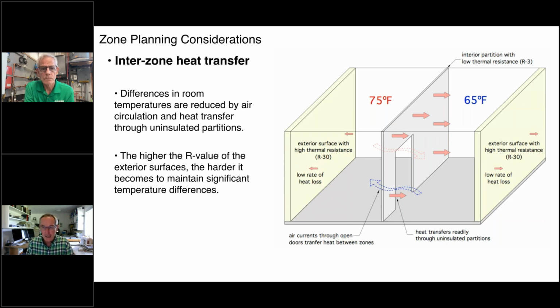Even if we shut off the heat in the space at 75 degrees, we would find that it would eventually equalize very close to the other temperature and vice versa. And the higher the thermal resistance of that building envelope, the more difficult it is to maintain significant temperature differences between these spaces. Now, if there's some reason where you really need to maintain significant temperature differences, you can insulate the partitions and basically keep the door closed, or possibly even use an insulated door. But most homes are not built that way. So again, consider interzone heat transfer and move away from the idea that I could keep bedroom number 1 at 65, I could keep bedroom number 2 at 75, and I can have an uninsulated partition between them, and both doors would be open.